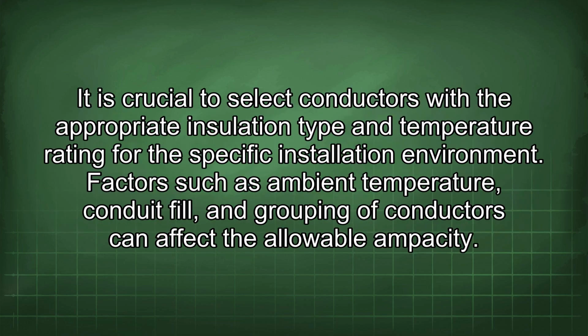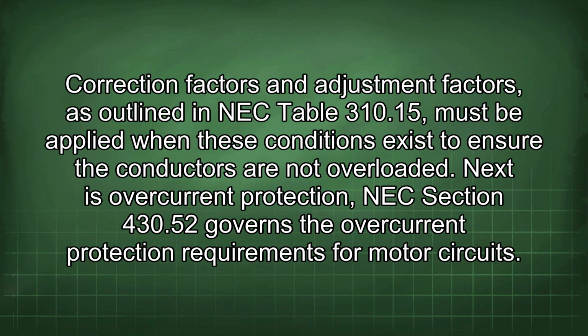It is crucial to select conductors with the appropriate insulation type and temperature rating for the specific installation environment. Factors such as ambient temperature, conduit fill, and grouping of conductors can affect the allowable ampacity. Correction factors and adjustment factors, as outlined in NEC table 310.15, must be applied when these conditions exist to ensure the conductors are not overloaded.